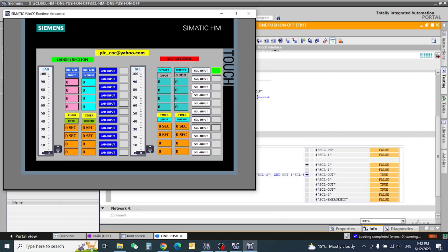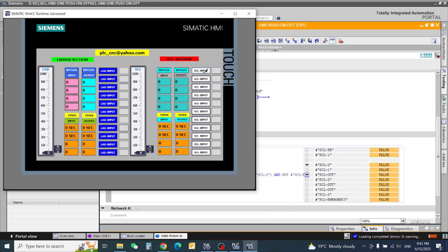You will see the SCL output continues coming when I switch off. I press emergency — emergency is ON and output is gone. Now emergency is OFF and output is coming back. With emergency ON I try to turn ON but the output is not coming. First I release the emergency, give the pulse again, and the output is coming. Thank you for watching this video friends.